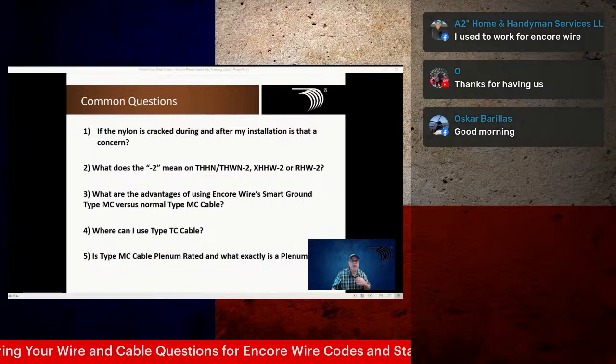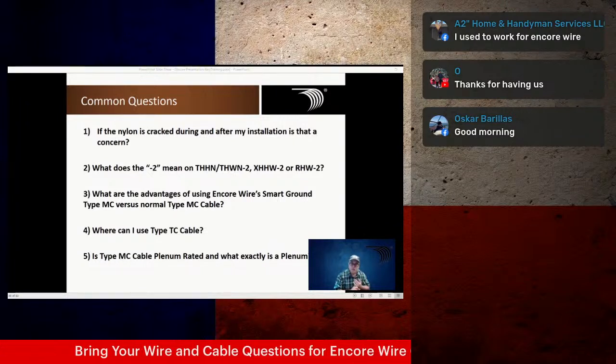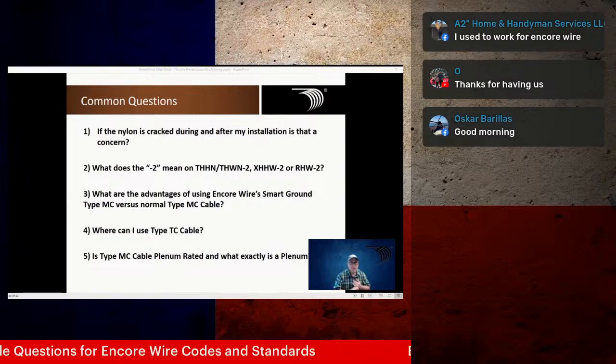All right. So what did we learn today? Nylon on THHN can crack during installation. It's sacrificial. But if you're going to be in an oil and gas environment, you have to make sure that that nylon stays intact. But again, if it cracks, no harm, no foul, not a problem.